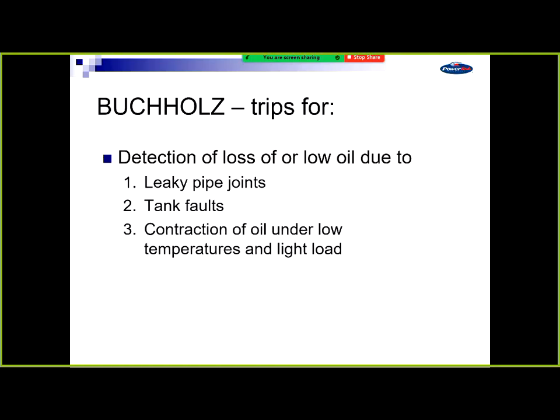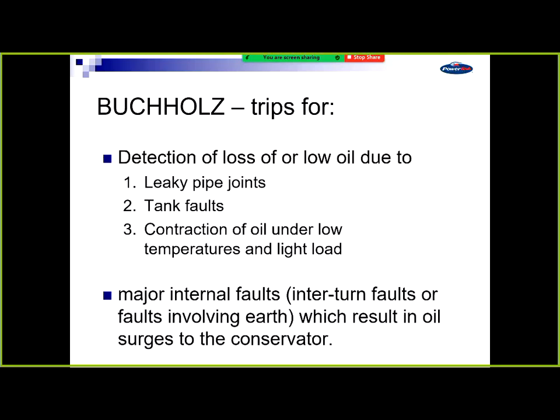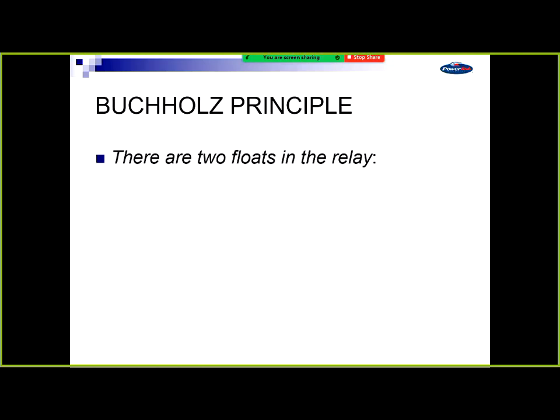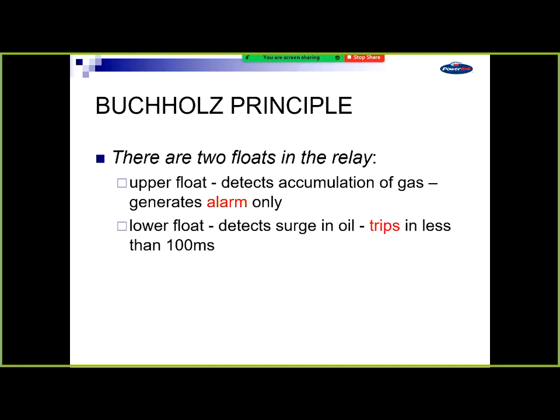Your Buchholz will trip for things like leaky joints, tank faults, contraction of the oil under temperature or faults, and major internal faults causing surges in your oil. So there's two floats within the Buchholz relay, an upper float which just alarms, and it's really there detecting gas, low-level faults, so you go and investigate further. Serious faults which cause a big fault internally will send a surge of oil through the transformer, and that will trip the lower float, which will trip the transformer. These are a mechanical device sitting in the transformer that just wires out to the protection relays, which just receive that input and take it out to the circuit breaker, and we start CB fail when that occurs, circuit breaker fail.